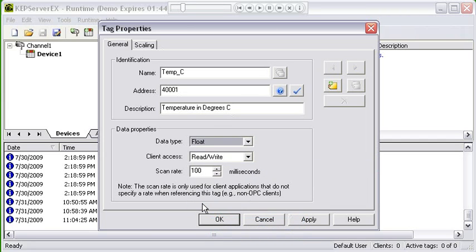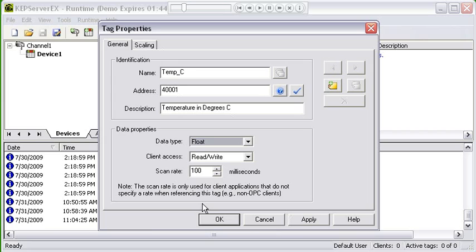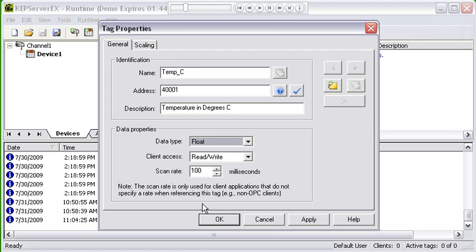If you want to know what data types are supported by certain addresses in the driver or what the default data type is, click on the driver help file for the driver you're using. Look in the addressing topic. You'll see a list for models or generically for the entire driver of all the addresses that are supported. Beside each address range description they'll have a section for data type, and the default data type is always bolded.